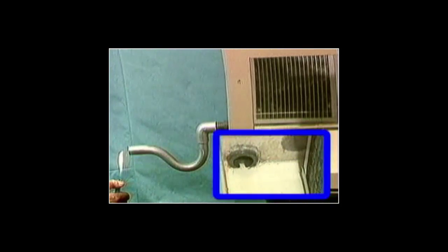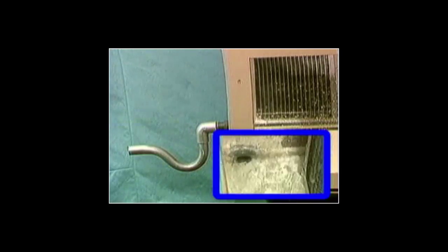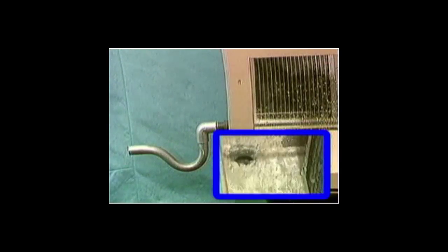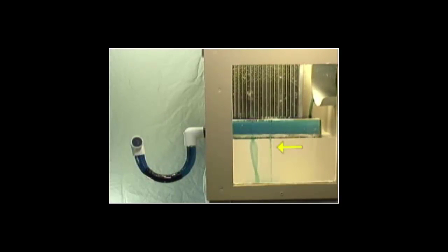Here, the effect of operating a system with an empty trap is illustrated. During startup for summer cooling, the empty trap acts like a missing trap, causing similar damage and contamination to the system and building. Debris and algae growth frequently block traps, as shown here, and cause drain pan overflow. This is one of the most common causes of building property damage and contamination.